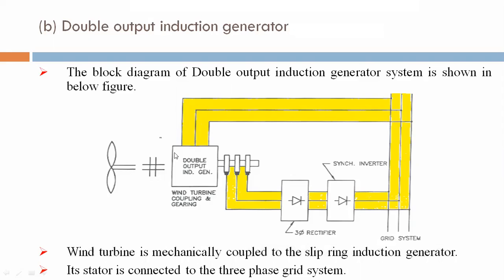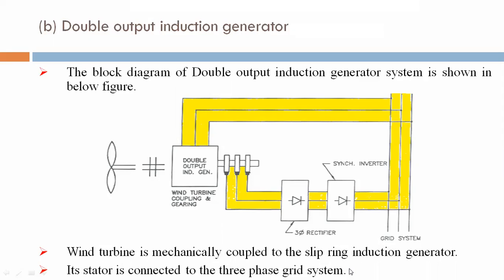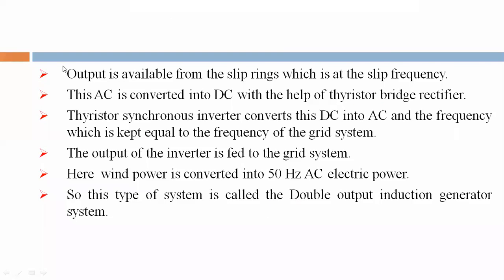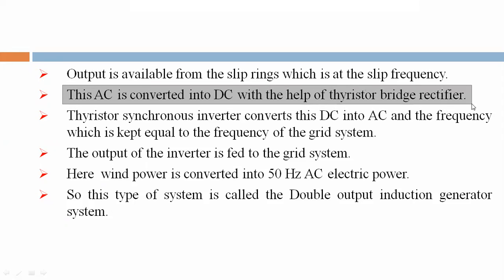The wind turbine is mechanically coupled to the slip ring induction generator. Its stator is connected to the three-phase grid system. Output is available from the slip ring, which is at slip frequency. This AC is converted into DC with the help of a thyristor bridge rectifier.